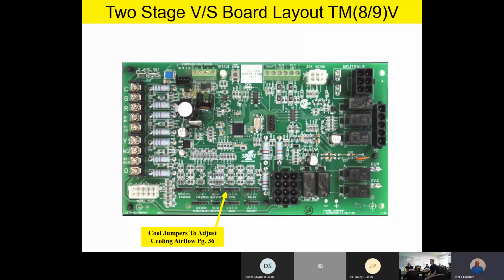Let me say that again. When you set up your cool and your adjust jumper, you're setting up your Y2 or your high speed airflow. If you have this on a two-stage unit, let's just make it simple. Let's say we have a 2.5 ton unit sitting outside, and we always set our airflow up for high speed cooling at 400 CFM per ton. So with a 2.5 ton unit outside, just for simplicity, our Y2 airflow is 1,000 CFM.